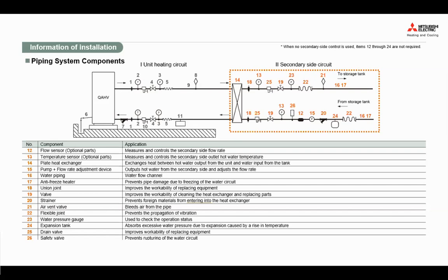And then in here, a lot of time we'll mention on the right-hand side, on the left-hand side, the unit heating circuit and the secondary heat circuit. So you will need to perhaps provide a plate heat exchanger, right? And then also all the hydronic equipment alongside with it: strainer, pumps, expansion tank, flexible joint, and the air vent. So all that is very similar to a conventional hydronic system when you incorporate that into, I guess, a more conventional system, let's say a boiler type of situation.